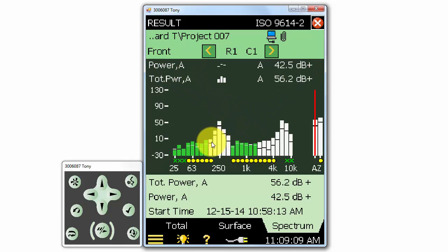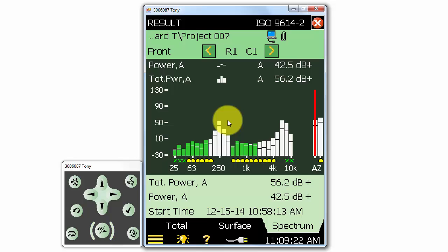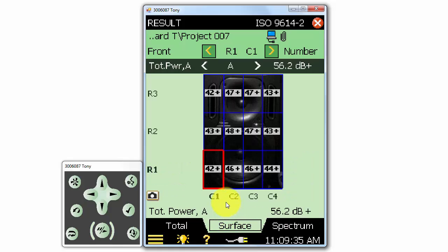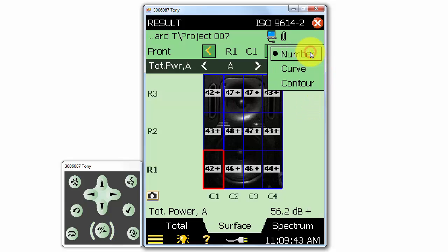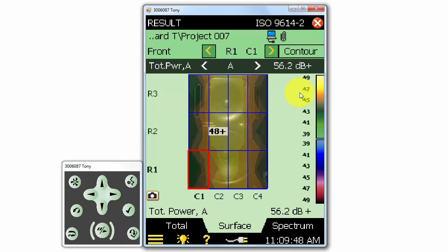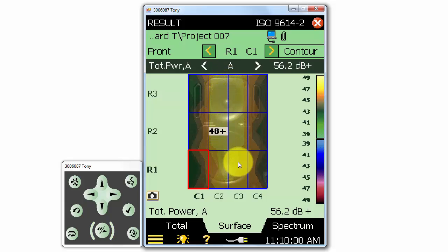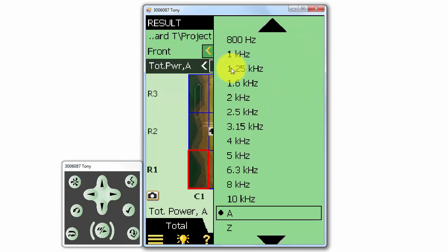The Results section has three tabs at the bottom. The Spectrum tab is where we can view the third octave sound intensity results for any segment. The white bands represent dominant sound energy coming from the sound source, and the green segments represent that the dominant source is from the background. The Surface tab will allow us to look at the results for any of the sides. The results can be shown as a numerical value for each segment, or we can calculate a map with curves or contours by selecting the menu at the top right. The default display shows the overall A-weighted energy on the measurement surface, and we could also select to display the map of any particular third octave band result.